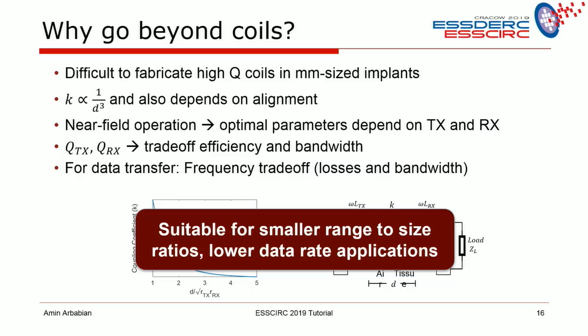The problem with far field RF transfer is that even in the body, at the couple of gigahertz of frequency we're going to use, the wavelength is very large. When the wavelength is large and your implant is small, there are a couple of problems that are fundamental, on the physics side of the problem, not even the circuit side. Number one is that the large wavelength means that, from a diffraction theory perspective, you can't focus the beam.